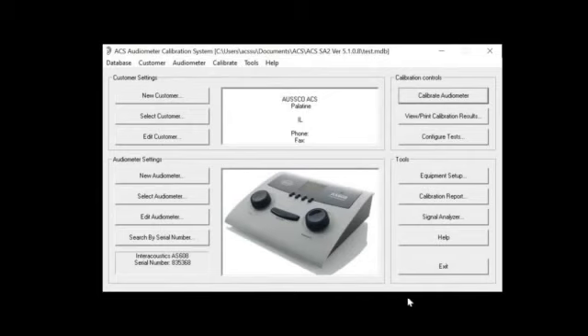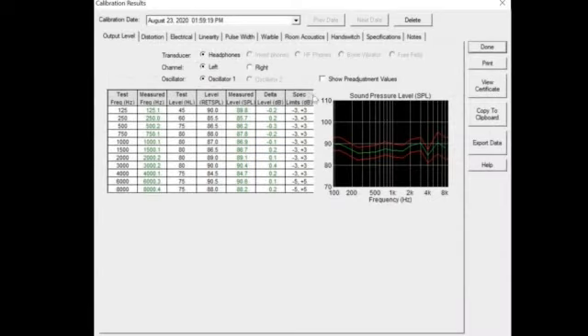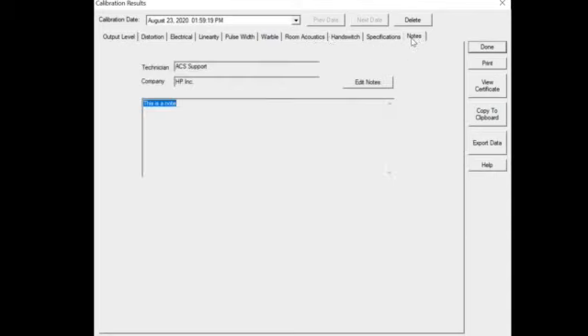They're going to stay there along with the pertinent information on your calibration data. So if in 3 years you want to go back in and reprint that calibration certificate, it has the microphone, serial number, the date of calibration, everything pertaining to that particular test. If I want to view it now to find out what it is, I can click on it over here. Here's the headphone level. I have that for the left ear. If I want to take a look at the right ear, I can come over here. If I want to show what it was on pre-adjustment, that was on the left ear. Bet you thought it wasn't going to show up. There it is. If I wanted to see what was going on with the notes, I can come back here and edit them if I'd like to.